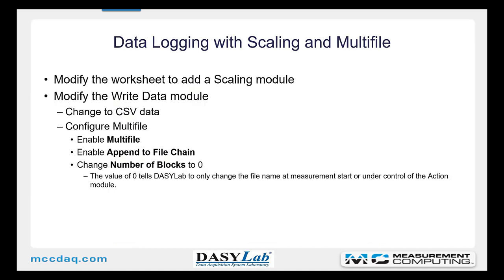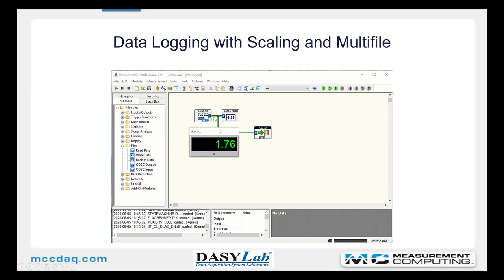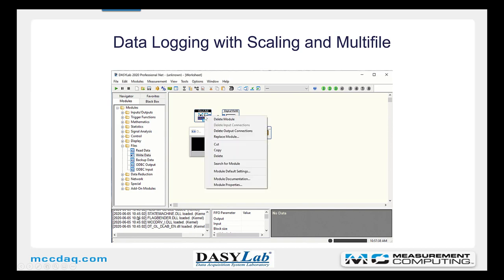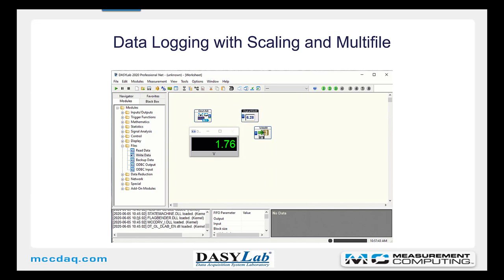Now I want to add scaling and the multi-file feature to the write data module. We're going to modify the worksheet to add the scaling module, rearrange everything in series, and then modify the write data module to change it to CSV data and enable the multi-file safety feature — this creates a new file every time you start the measurement. After rearranging the existing worksheet, I'll start by deleting the connections from the analog input, then move the modules to make room for a scaling module. Open the mathematics group and select the scaling module.